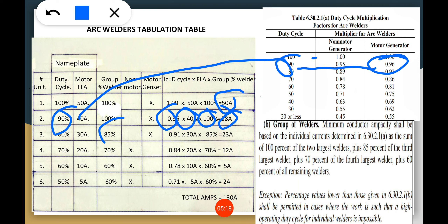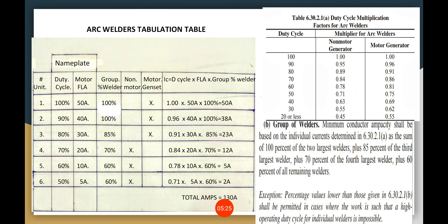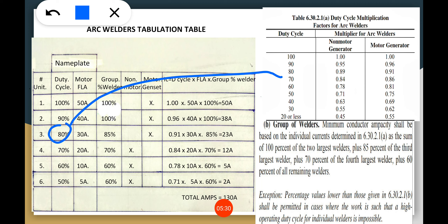For the third unit: 80% duty cycle — motor generator gives 0.91 from the table — times 30 amperes times 85% group welder factor = 23 amperes.